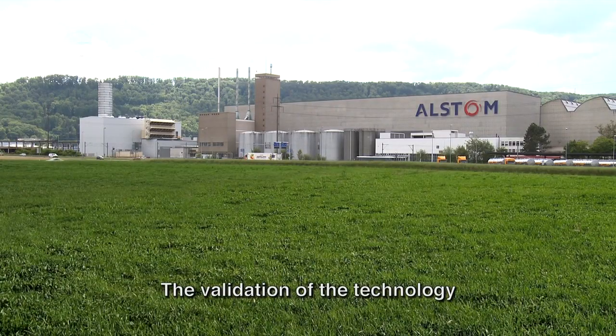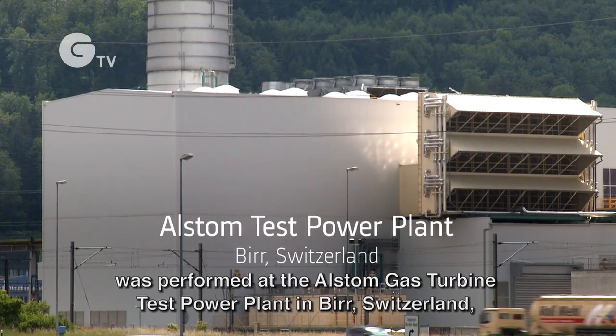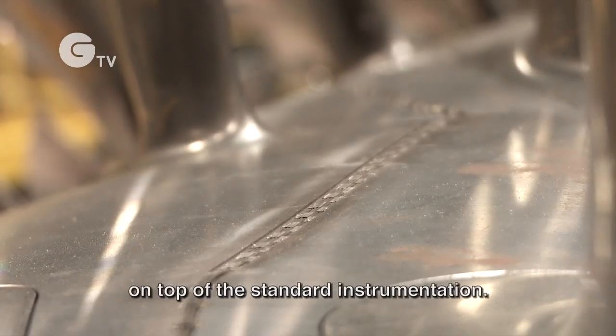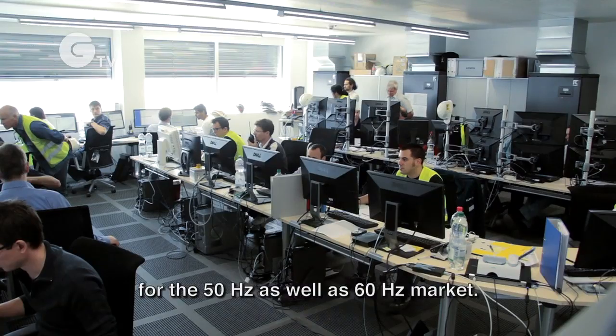The validation of the technology was performed at the Alstom gas turbine test power plant in Birr, Switzerland, using 4,600 measurement locations on top of the standard instrumentation. The successful validation resulted in the launch of both next generation gas turbines for the 50 hertz as well as the 60 hertz market.